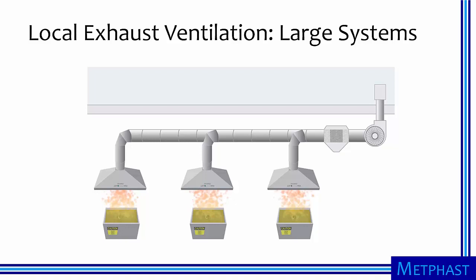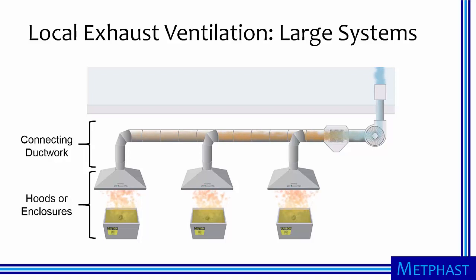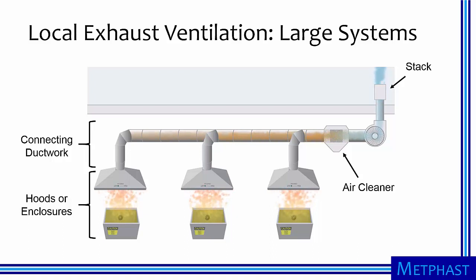In contrast, local exhaust ventilation systems evacuate contaminated air at the source. These systems can be very large, such as the multi-canopy hood system shown here. Multiple hoods or enclosures are used to evacuate contaminated air where it is produced. The contaminated air passes through connecting ductwork and an air cleaner, and is then exhausted outside the facility through a stack. We will spend most of our time today on local exhaust ventilation systems because these systems are most effective at reducing exposures in the workplace.